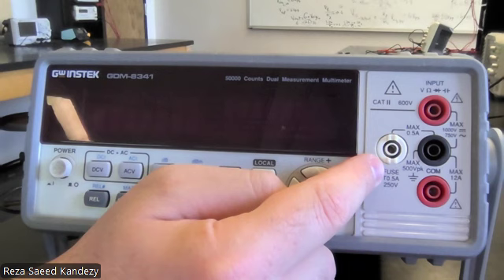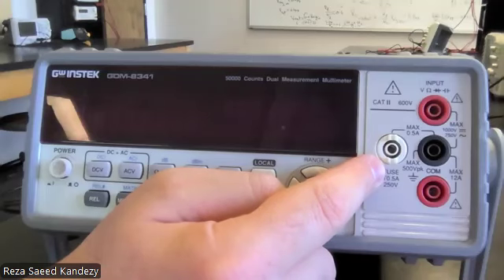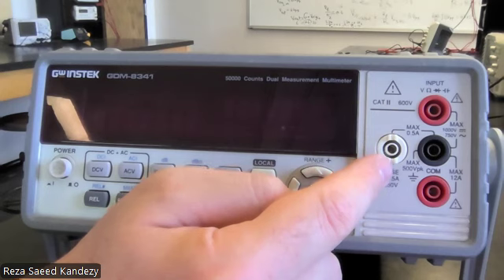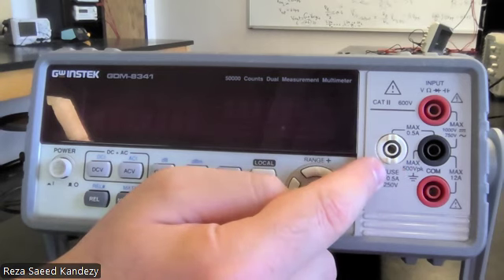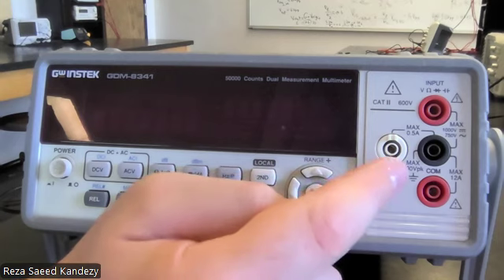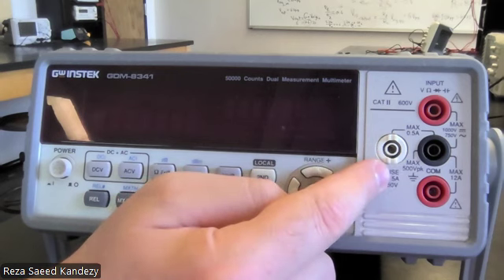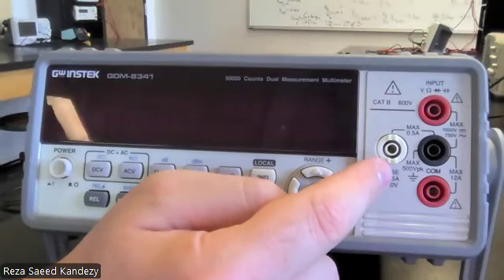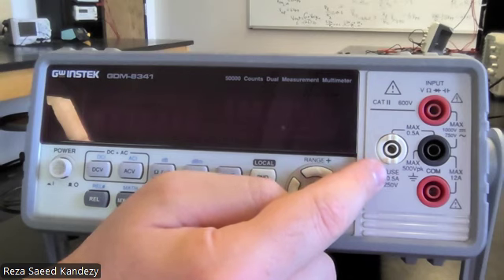Or safety ground, or EMC, electromagnetic compatibility issues. It would connect to either the safety ground port of the equipment or the circuit, or the shield that is on the circuit to reduce noise and electromagnetic interference. So again, you don't use that, but if you wanted to make a very precise measurement, you use that for noise rejection and safety grounding or reference grounding. It should not get connected to the live part of your equipment or circuit.